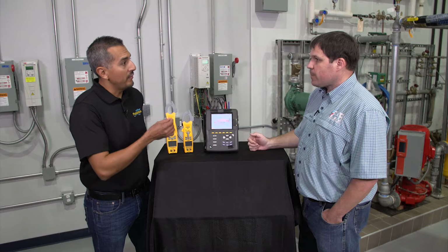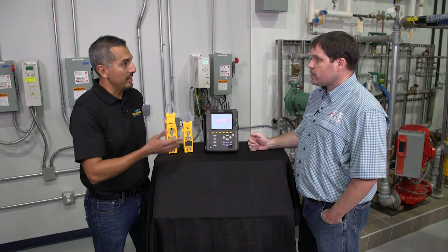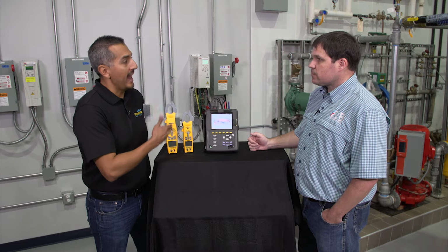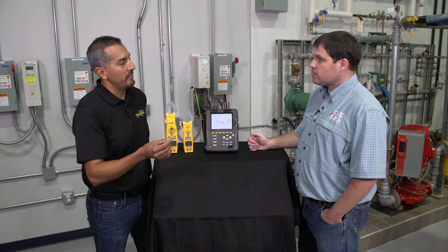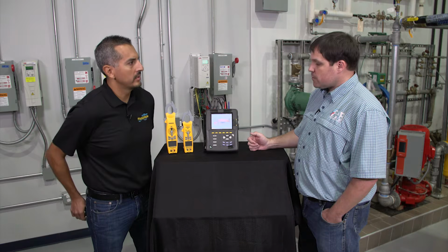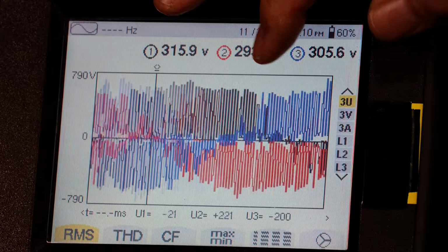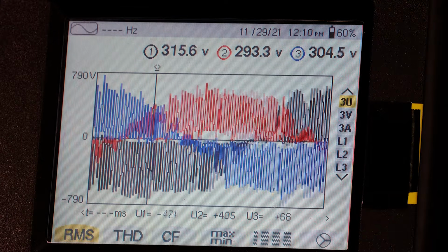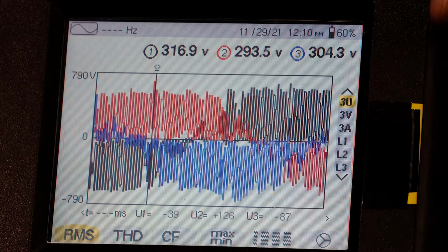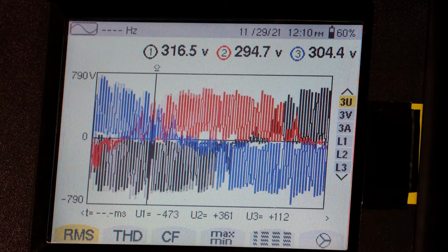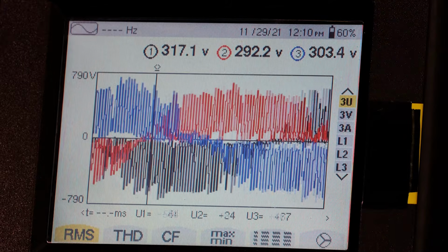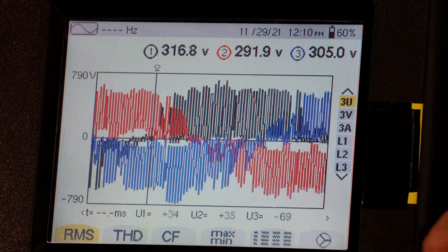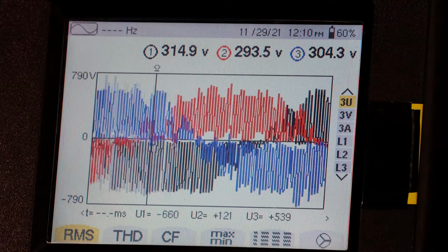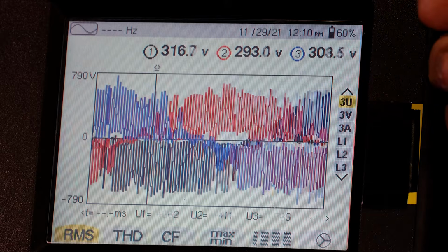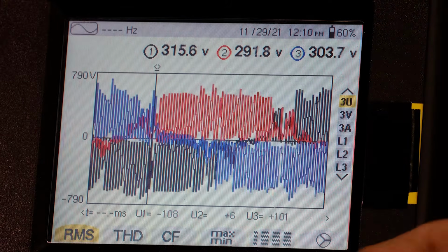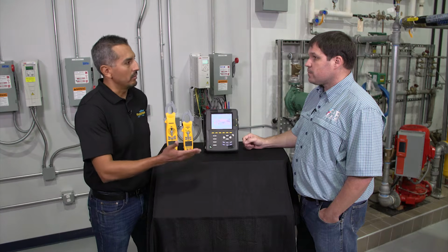Okay, so in the field, if a user isn't using a meter like the Fieldpiece wireless clamp meters with filtering built in, what are some real world ramifications a technician could come across? Good question. Between the average and the peaks in this signal, you could have 10 or 20% or more deviation. If you have that much deviation in your voltage measurements while doing tight troubleshooting or analysis on the motor or VFD side, that 10 or 20% inaccuracy could greatly affect the outcome, potentially leading to a misdiagnosis of the system.